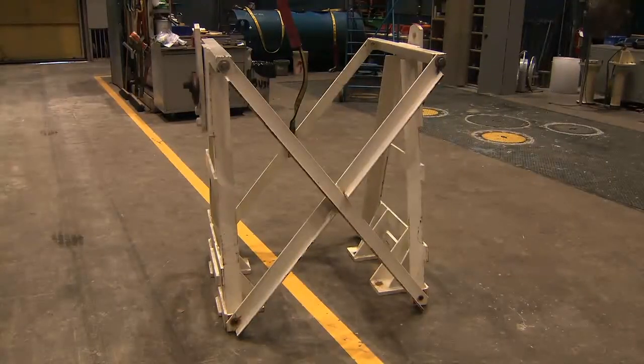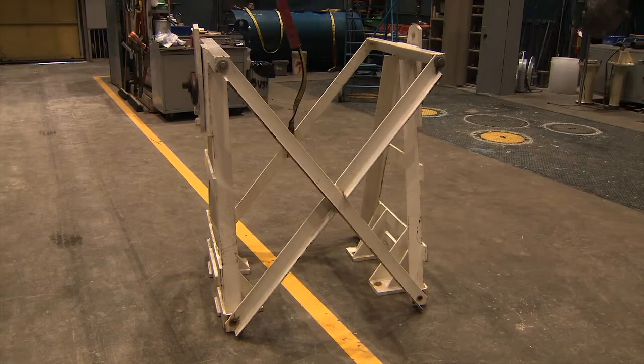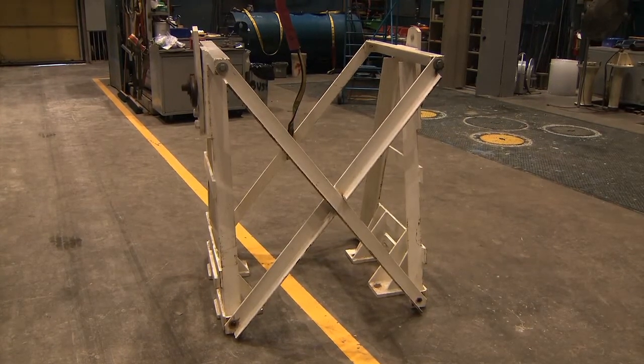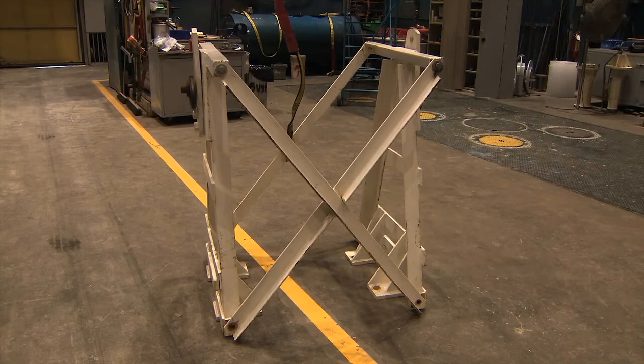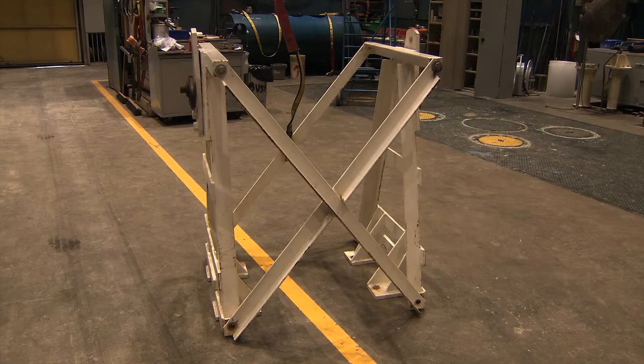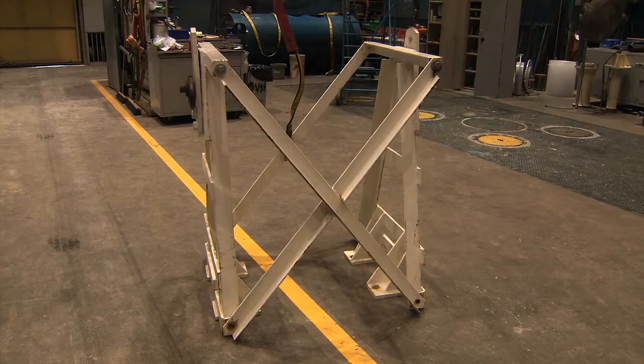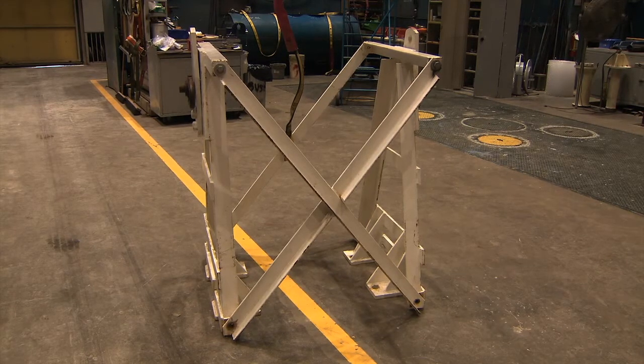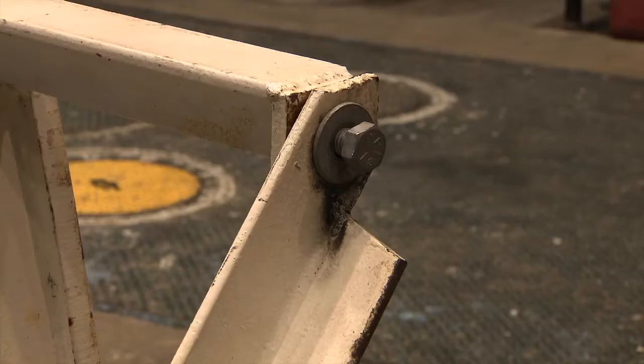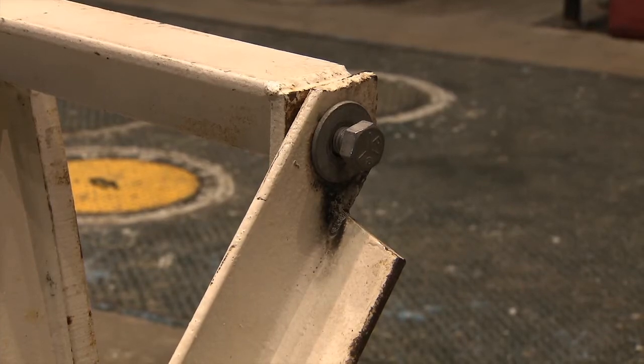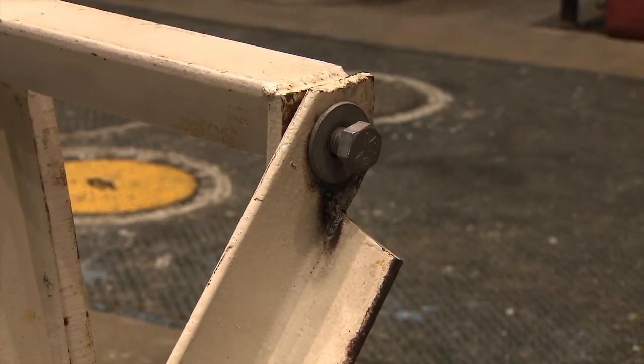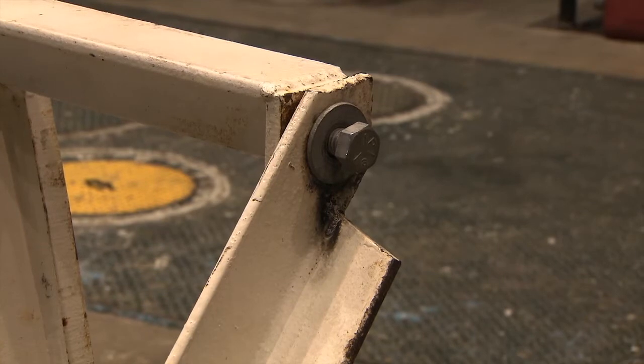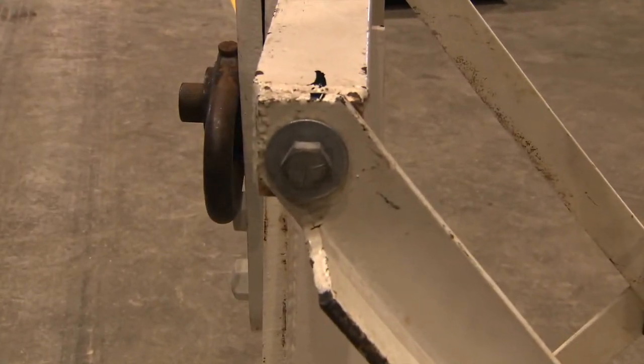In order to remove the bushing from the transport carrier, a lifting jig, as shown here, must be attached to the bushing so that it can be raised up from the transport carrier and also pivoted into an upright position for placement into a service well. The lifting jig has a crossmember on one of the sides that must first be removed so that the jig can be fitted onto the bushing while it lies on the transport carrier.